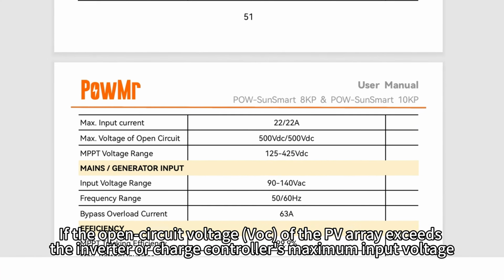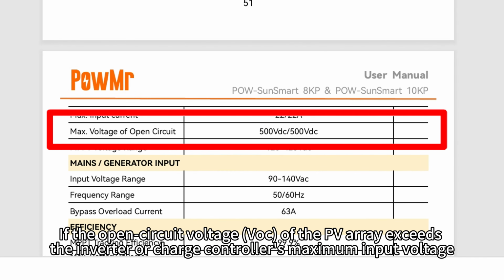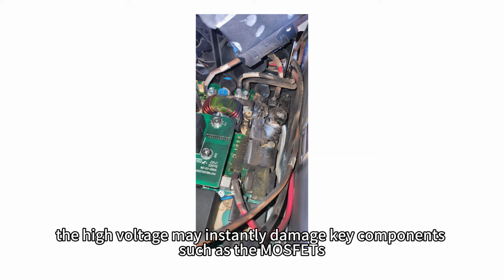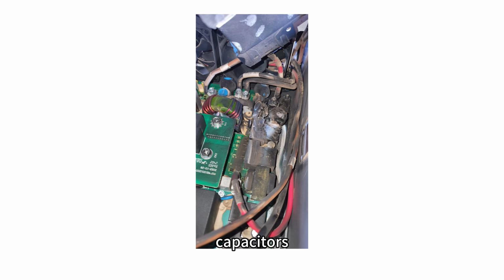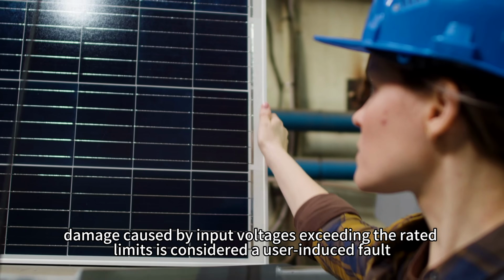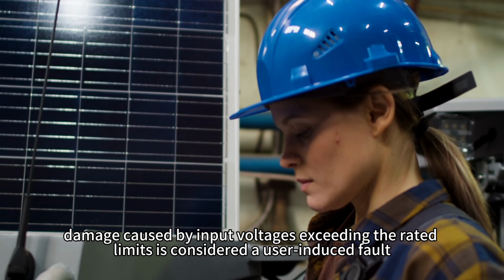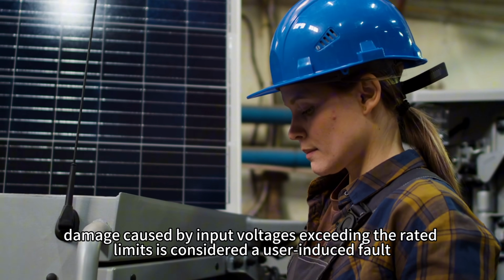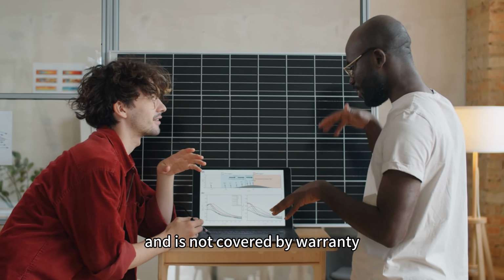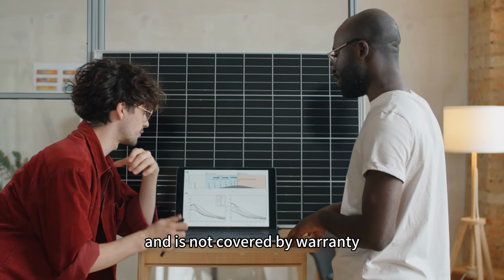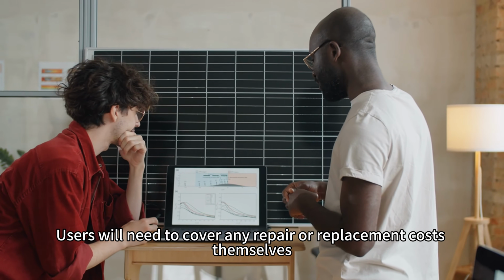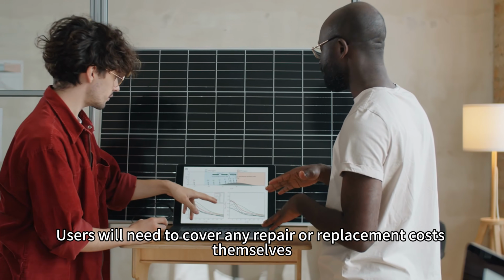If the open circuit voltage of the PV array exceeds the inverter or charge controller's maximum input voltage, the high voltage may instantly damage key components such as the MOSFETs, capacitors, or driver chips at the input stage. Furthermore, damage caused by input voltages exceeding the rated limit is considered a user-induced fault and is not covered by warranty. Users will need to cover any repair or replacement costs themselves.